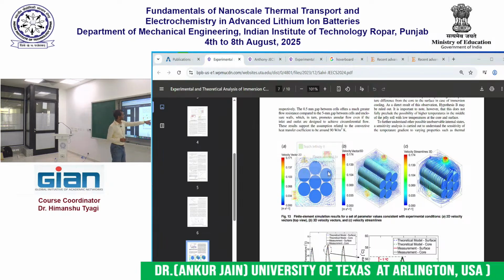We have learned in previous lectures that the thermal conductivity of a lithium ion cell is very poor, 0.2 watt per meter Kelvin or so, right? And therefore, this problem of temperature gradient inside the cell is inevitable. There will always be a temperature difference between the core of the cell and the outside surface. The only way to prevent it is to directly cool the core of the cell. Anything that I do to cool the outer surface will cool the outer surface effectively and will not cool the core effectively. That gives us a motivation to investigate how we can possibly cool the core of the cell directly.